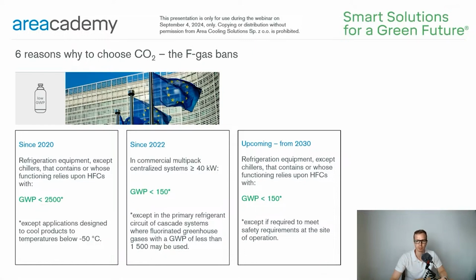The next ban was applied to commercial multi-compressor centralized systems over 40 kilowatts. Since 2022, refrigerants with a global warming potential factor equal to 150 or higher cannot be used anymore. For such systems, for example in supermarket applications, we already started to use natural refrigerants like CO2 or propane, or slightly flammable A2L refrigerants.